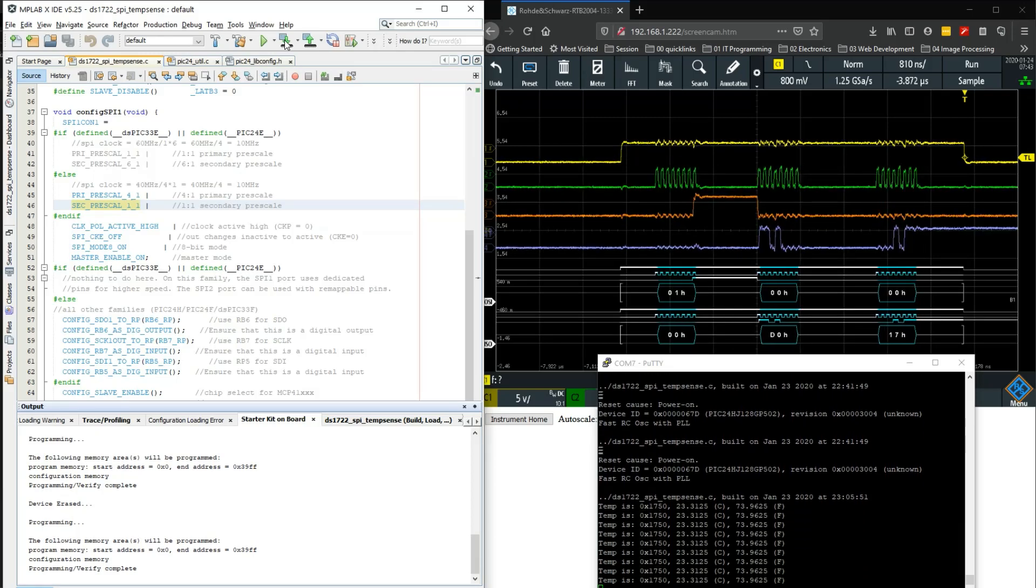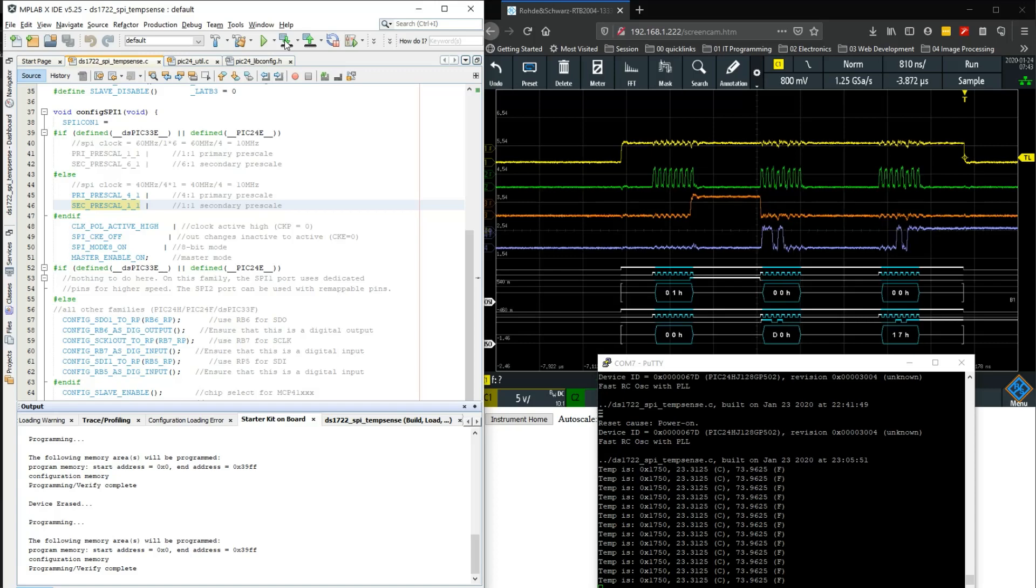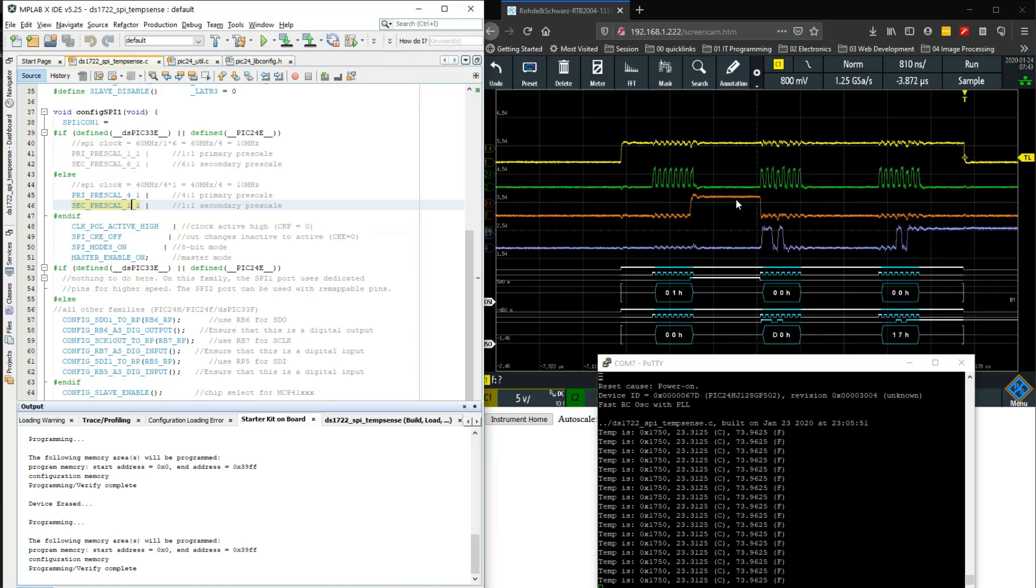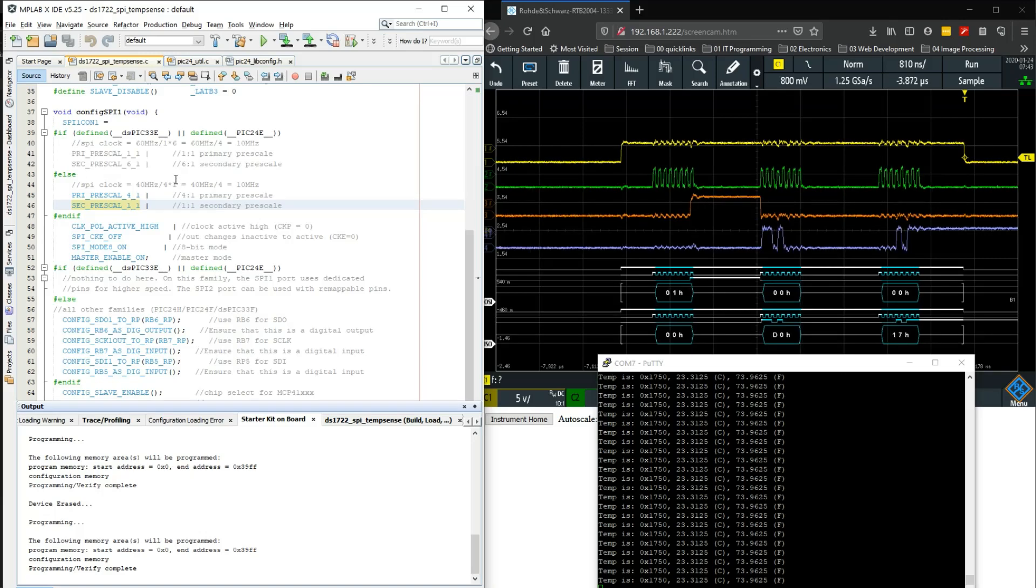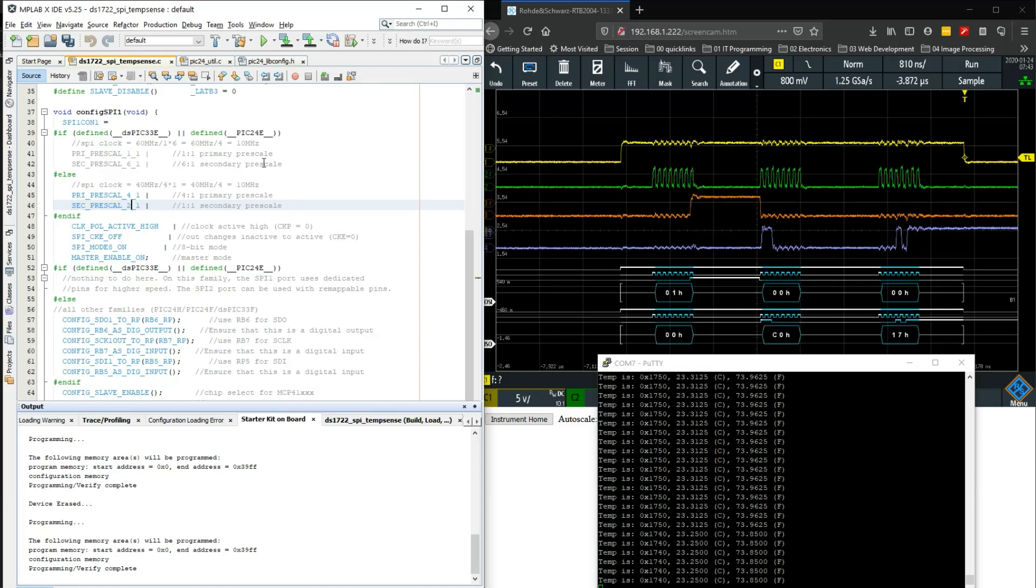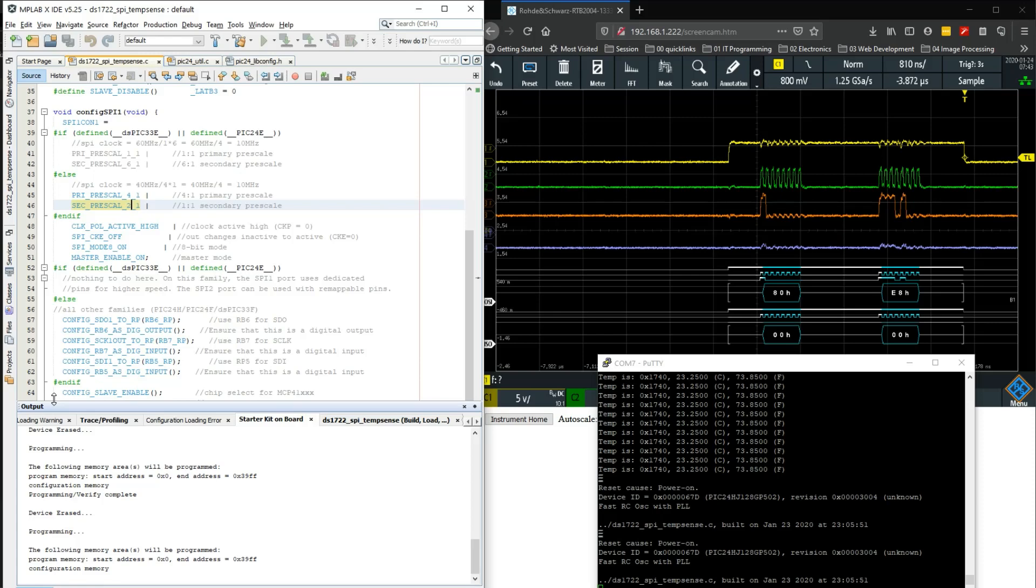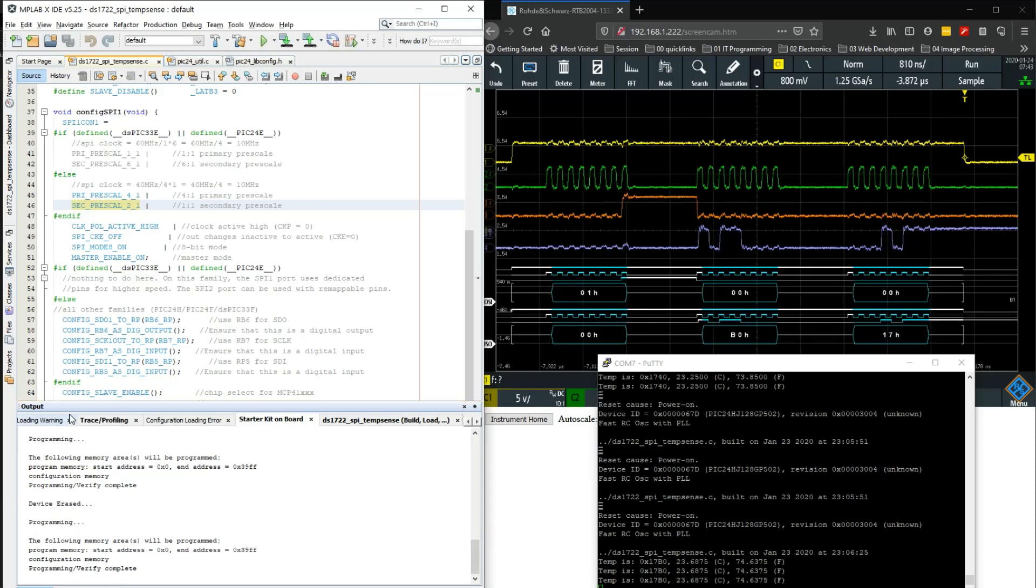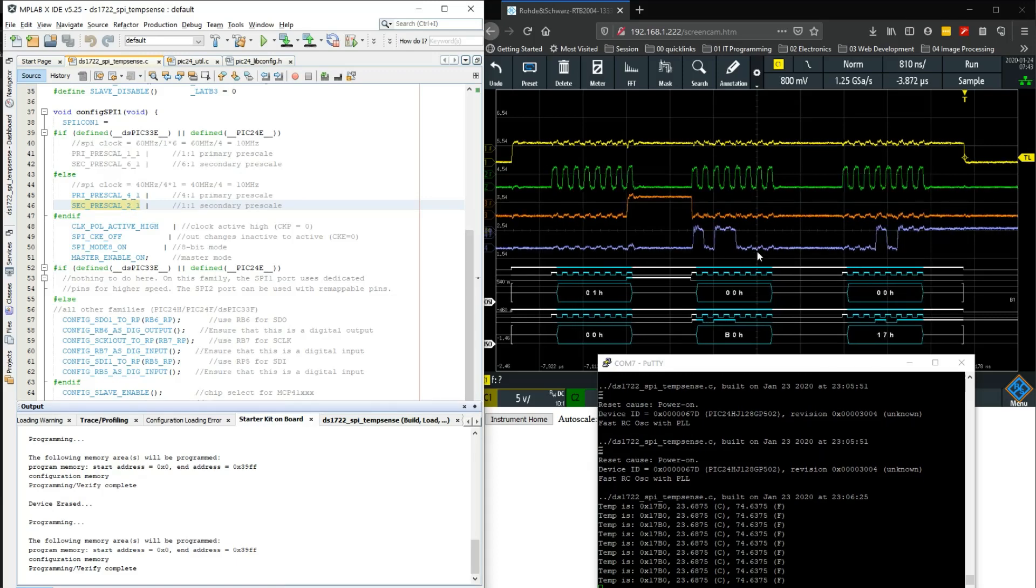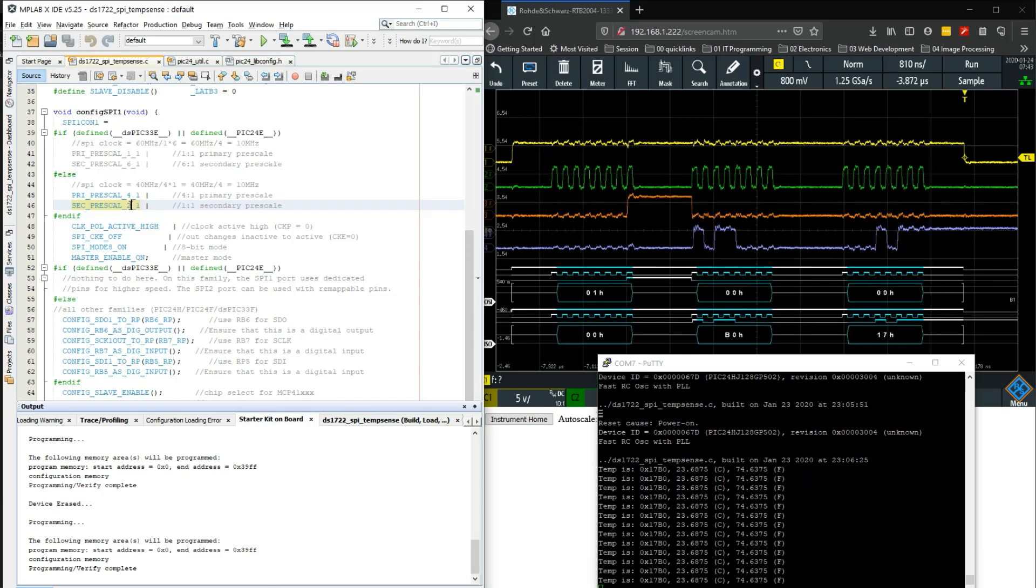Now you can see that the biggest change here is that everything's gotten faster, twice as fast. So setting the prescaler to one-to-one makes everything faster. Doing a two-to-one just makes it a slight bit slower. And you can change this. The reason why this is happening is because sometimes if your wires and cables and all those stuff don't really like the additional lengths, sometimes the values may not be coming up correct. So if that happens, you change the prescale up here and things will kind of get a little bit better.